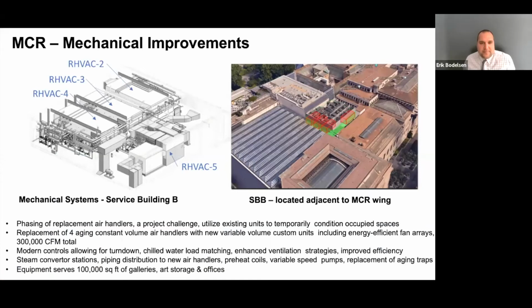As Henry mentioned, the project also provided the museum with the opportunity to improve mechanical system support in the MCR wing. You can see the location of the equipment directly adjacent to the wing in the graphic on the right. Some highlights of the upgrade include replacement of four constant volume air handlers with new variable volume custom units, including efficient fan arrays—about 300,000 CFM in total, a pretty substantial number.